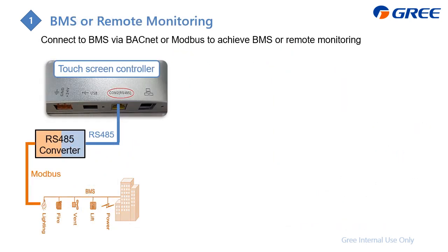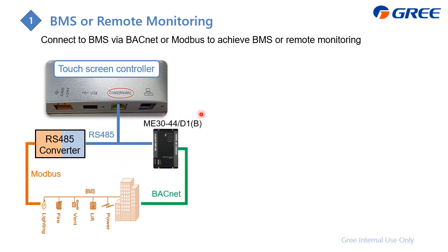Before we introduce our products in detail, I'd like to introduce how we can connect the centrifugal chiller to the BMS system. This is the touchscreen controller on the LV centrifugal chiller, and at the back of it there is an output. From here it already outputs the RS485 signal, and then you can connect to an RS485 converter and then connect to your PC, and this is actually the Modbus protocol. And you can also select BACnet. For that one you need to select our Gree ME30. From this device, the output will become BACnet. Also, you can connect to the computer, which is the BMS system.